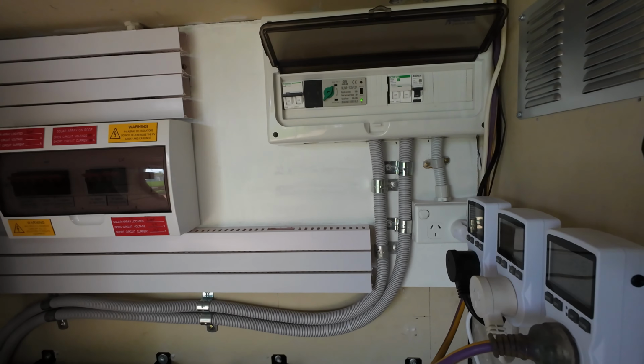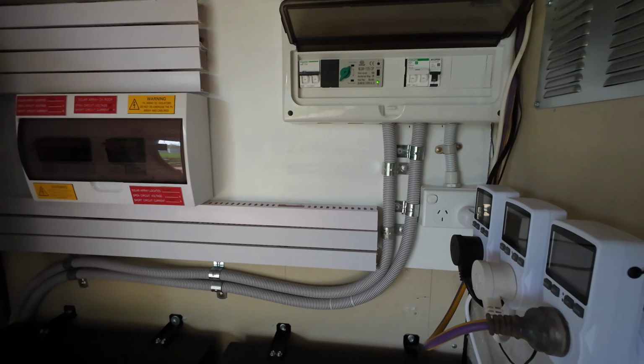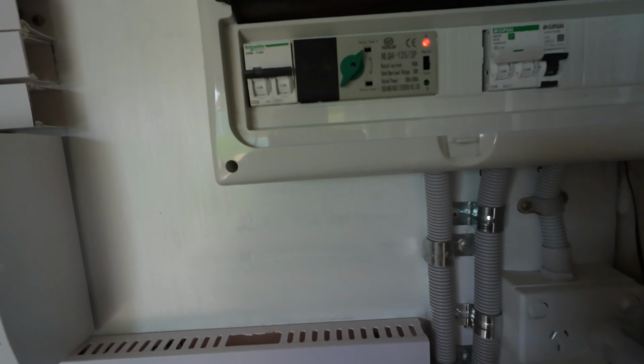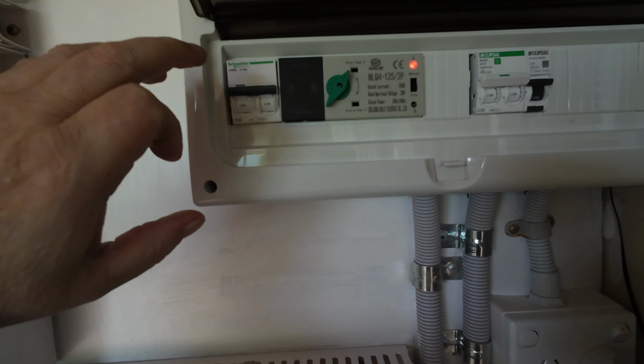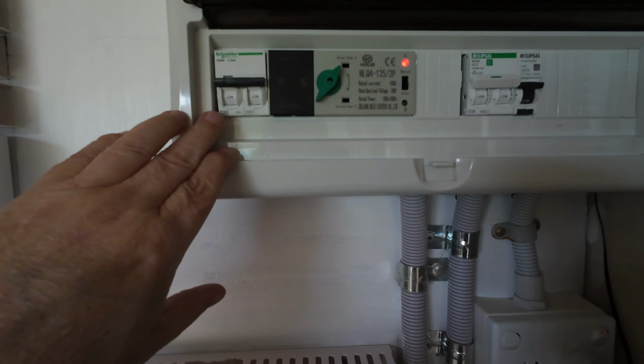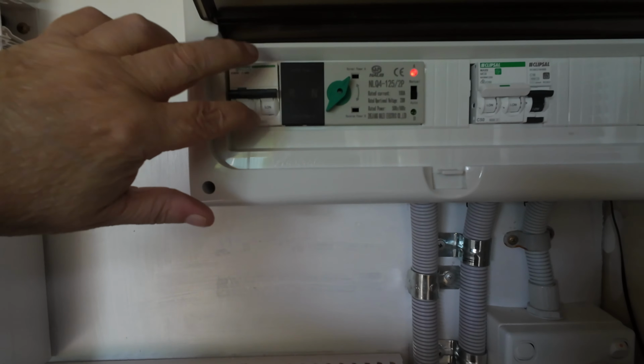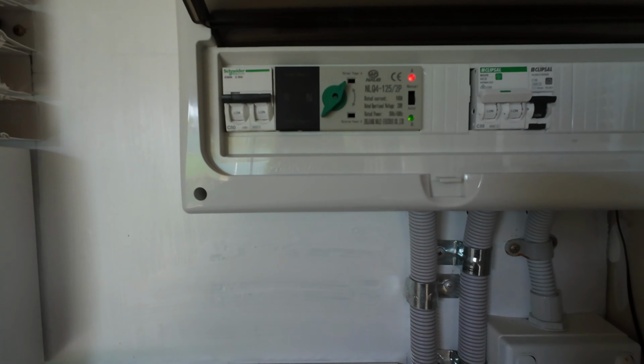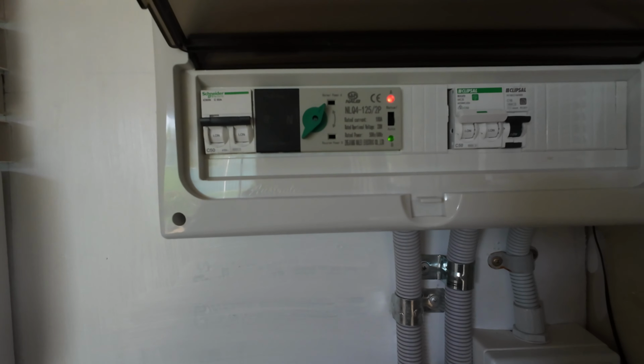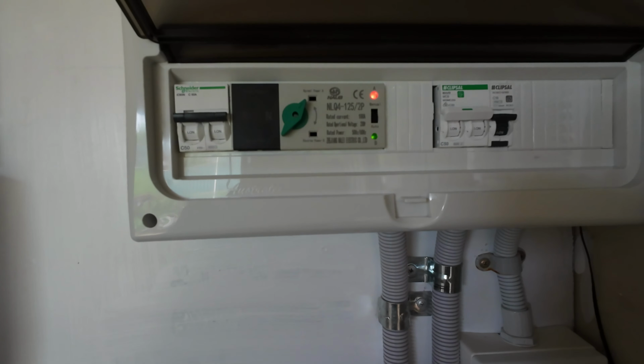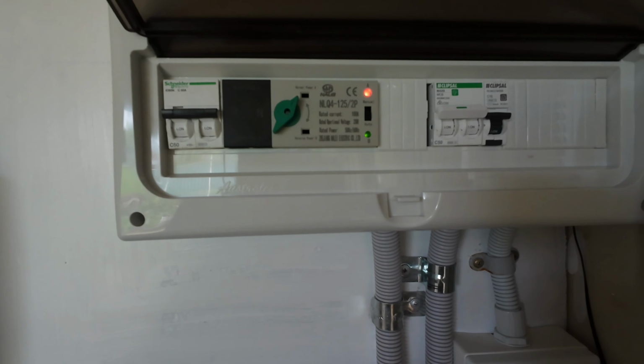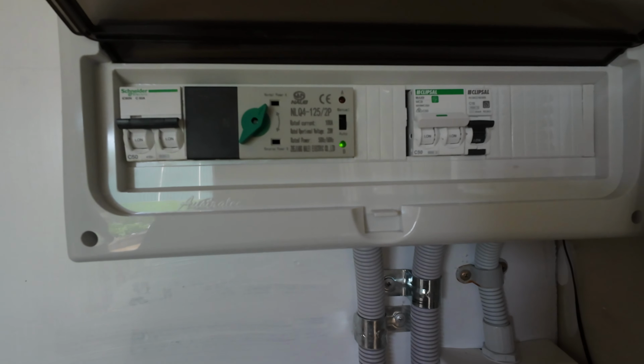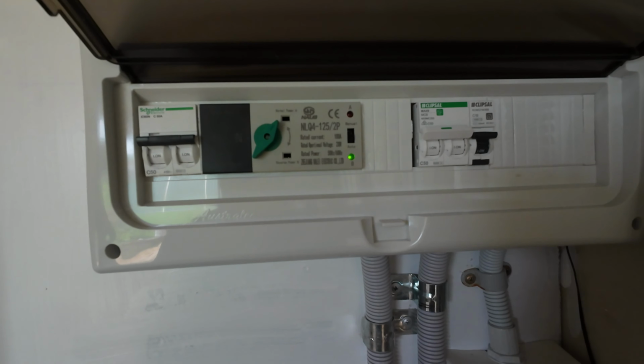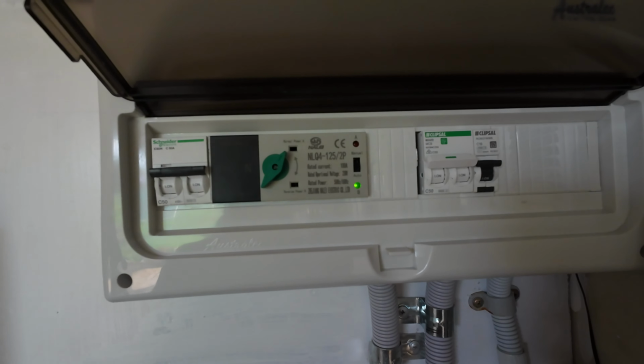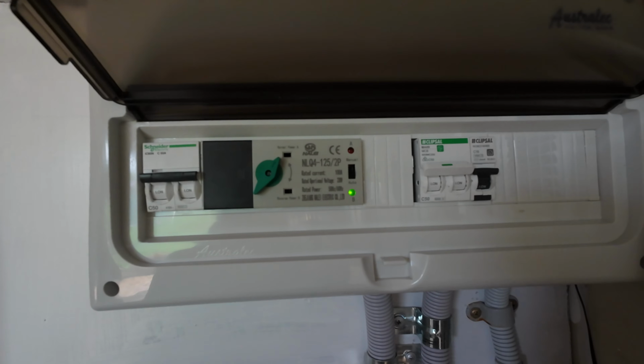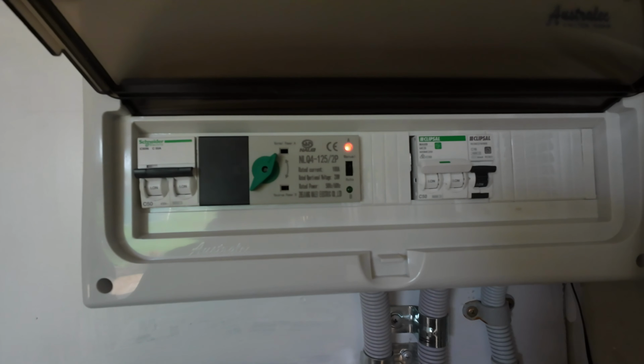You can have a hybrid system on your house. Wire your grid to the bottom switch, and put your hybrid inverter on the first switch, and have that normally feeding your house. So most of the time you'll be running off grid, and if your batteries get low, then it'll switch to the grid and you'll have the grid as a backup. And that's what a lot of you have been saying: we'd still like to keep the grid as a backup, Chris. Well, that's a legal way of doing it because this unit totally disconnects your grid from your house.